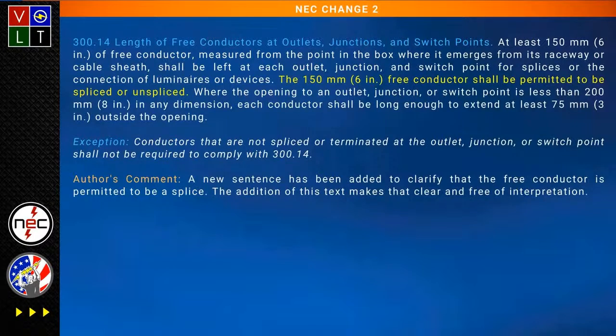It's funny because I trolled this on my Nat King Code page and got a lot of the code people going. This was Mike Holt's 2011 public input saying the length of the free conductors should be unspliced, and it failed. Now Mike Holt comes back for this cycle with a public input saying it actually needs language that says it can be spliced, which I thought was hilarious, because I trolled it since there was a myth from inspectors saying you have to have unspliced 6 inches, and if you don't, they won't pass you. There was a lot of heat on that one, and we tangled with inspectors on it, but we got it fixed. It was funny because they were acting like Mike Holt's public comment actually passed.